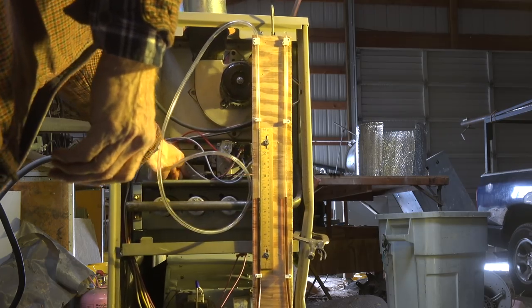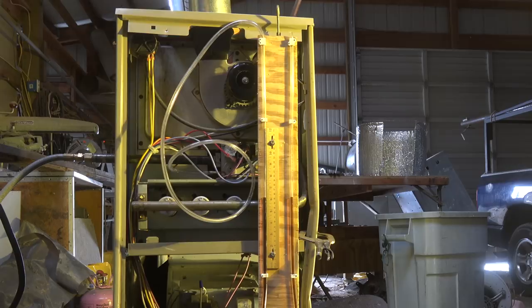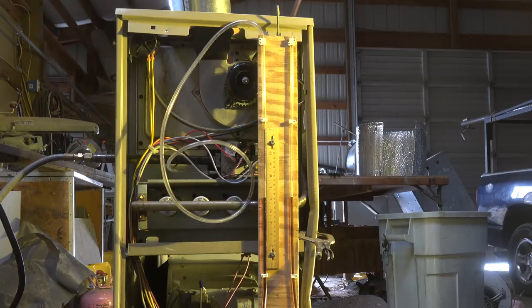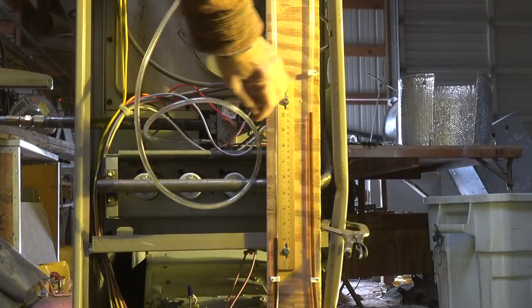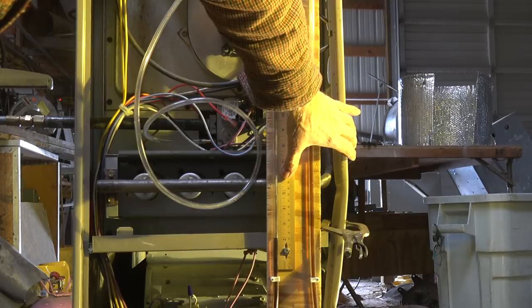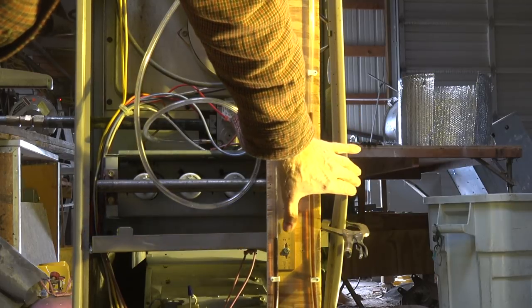Okay, now that's connected and I'm going to go ahead and put gas to this, and I should show about eight inches water column. Now when I look at this, I set this at six - one, two, three, four - it's pretty much right on, it's a little bit under, which is probably what the pressure is.